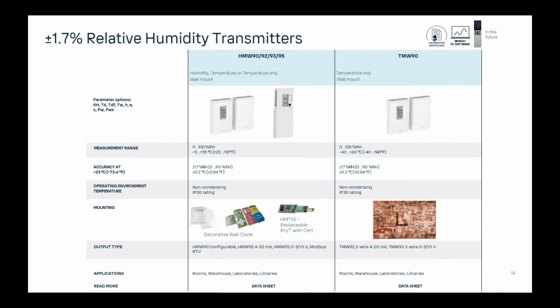Continuing along with the offering, this is a little bit different. It doesn't offer any remote probe options or cables or removable probes. But we have our HMW 90 series, so we refer to it as the 90 series. You'll see on the right, we have a temperature only model. So this is great for warehouse monitoring, rooms, lab spaces that don't need washdown rating. So this is only IP30 rated, whereas everything else was either IP65 or IP66. They do still come with traceable calibration certificates, ISO 9001 compliant. The difference here is that we actually don't adjust or calibrate these. They come with a replaceable humidity and temperature module that comes with its own certificate. So that can be changed in the field by anyone.